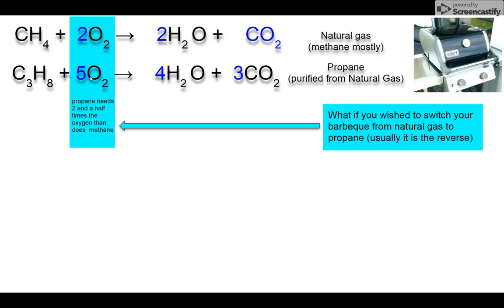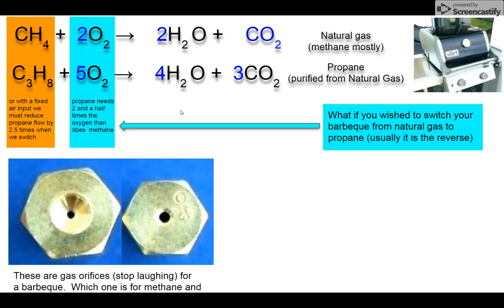Now, in a Bunsen burner, that's easy. You just unscrew the chimney till the windows letting in the air are two and a half times bigger. But I guarantee you, the barbecue, your home furnace, and your hot water tank do not have adjustable air intakes. The only thing you can adjust is the fuel. So if you can't increase the air by two and a half times, then you need to cut down the fuel by two and a half times. And this is how they do it. These are changeable gas orifices for furnaces and barbecues to change them from one fuel to another.